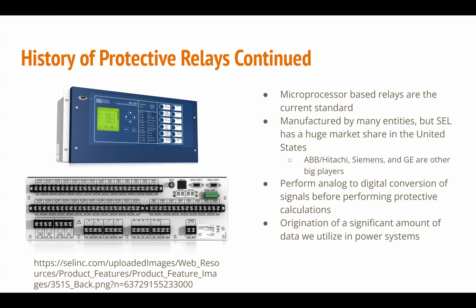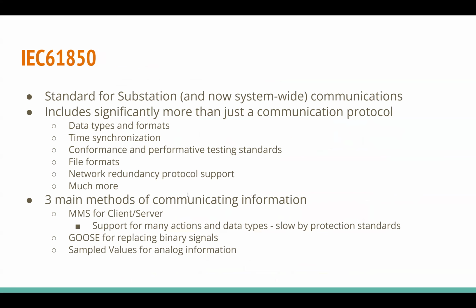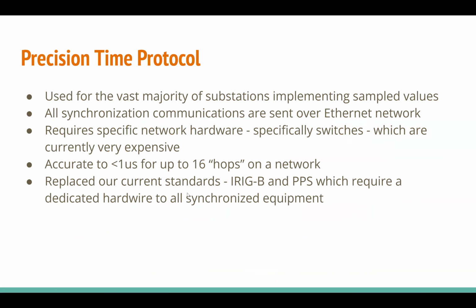Our sample value streams and GOOSE messages all come in now over just our Ethernet connections. So we can eliminate literally every single connection on the back of this except for our Ethernet, which is really nice. Time synchronization, though, is difficult to set up properly for people who don't understand it. As training happens, people will understand precision time protocol better and have fewer problems with it.